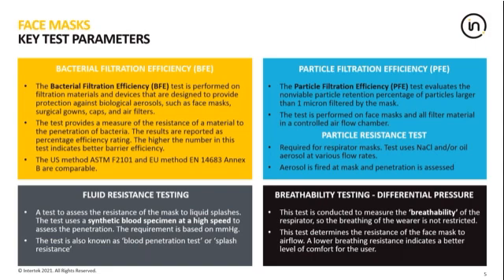We'll now look at particle filtration efficiency testing, PFE, and particle penetration tests. The purpose of this is to determine if any particulate matter can penetrate the mask. In the medical mask standard, the test ASTM F2299 uses a latex polymer particle aerosol of 1 micron in diameter, and these are impacted against the mask in a controlled airflow chamber. The number of particles which are retained by the mask are counted to provide a measure of filtration efficiency.